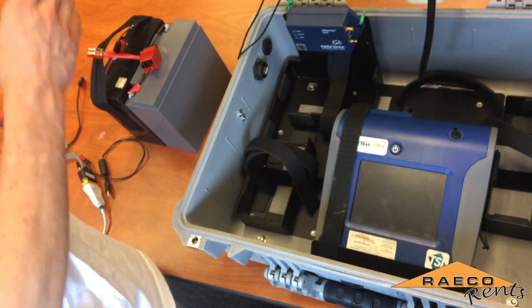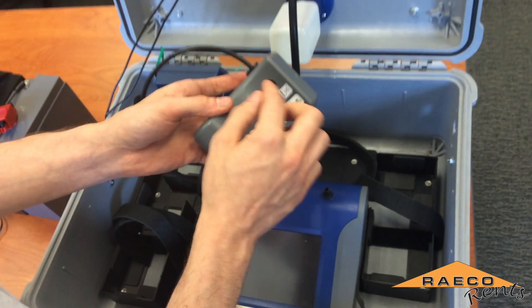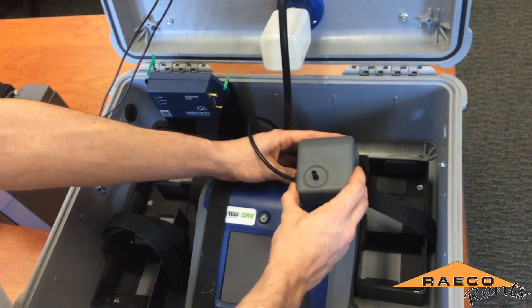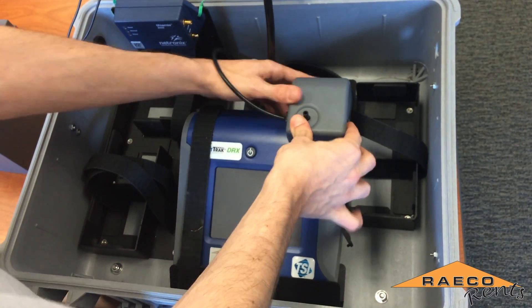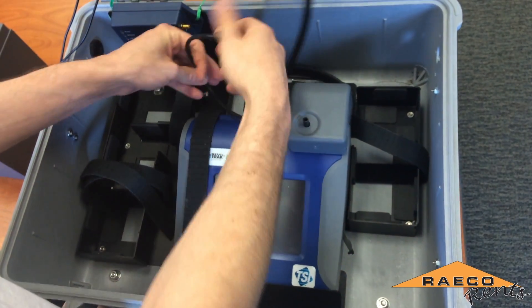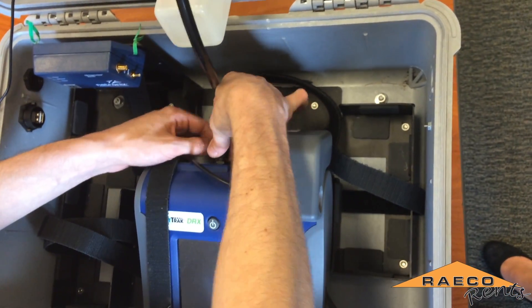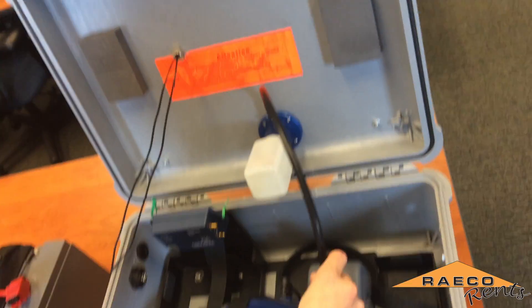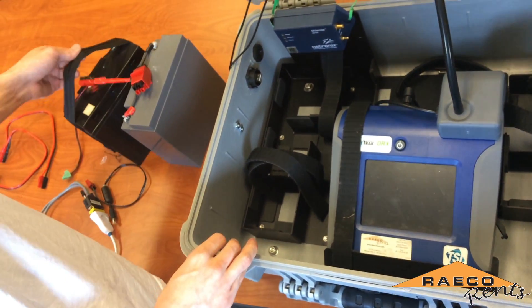We have an AutoZero module that we're going to install on this unit. It has a port that you connect to the sampling inlet on the DustTrak, which should just snap into place. Then you would connect this cable to the port on the back of the DustTrak, which then turns to lock in place.